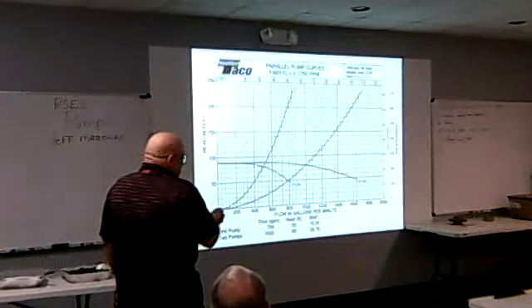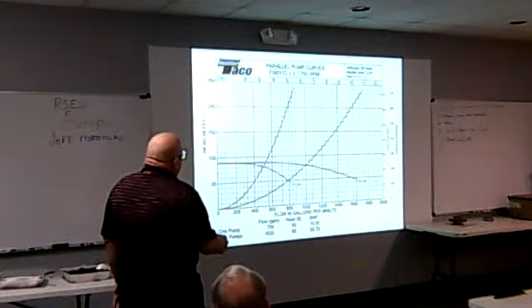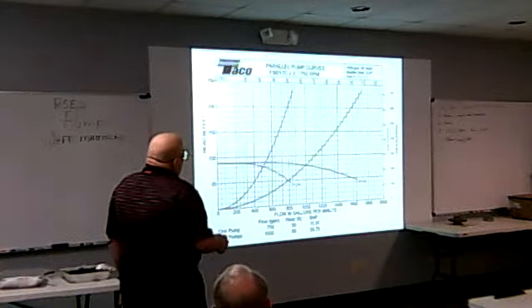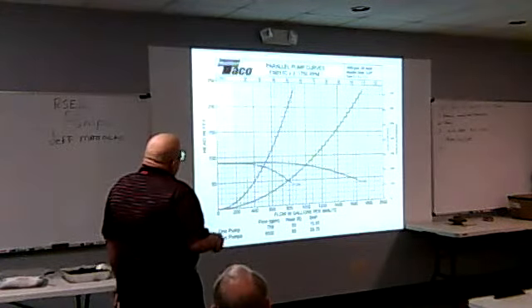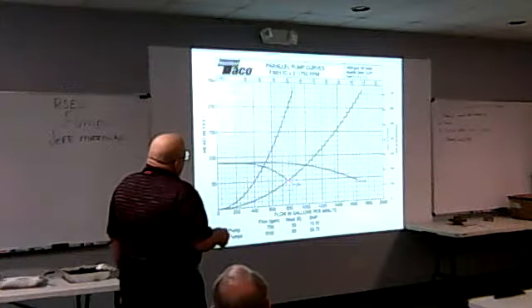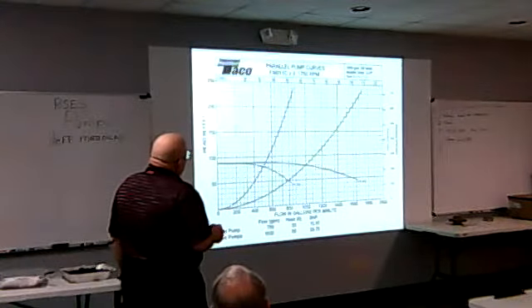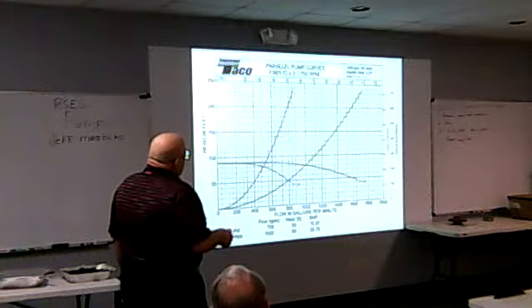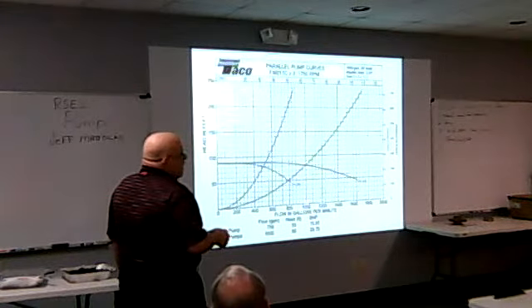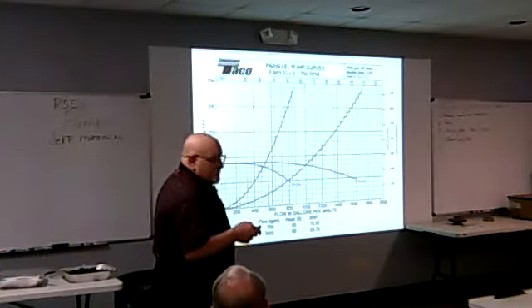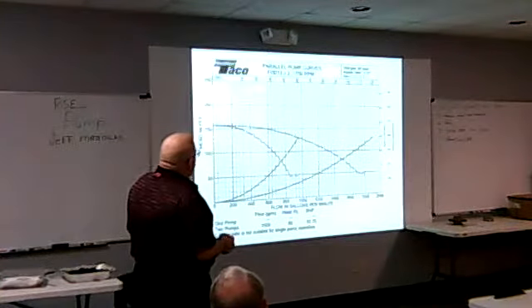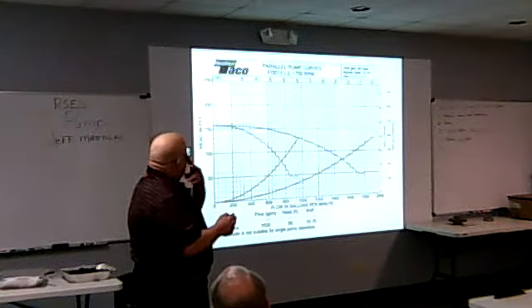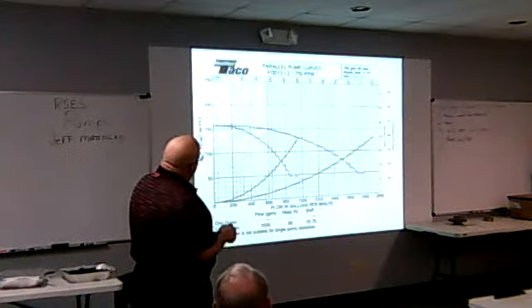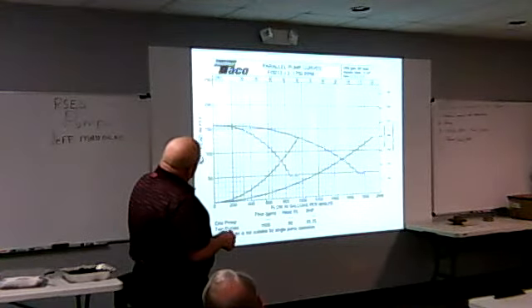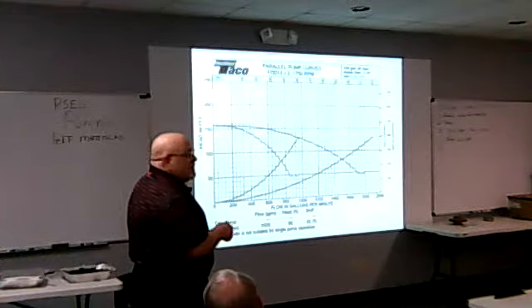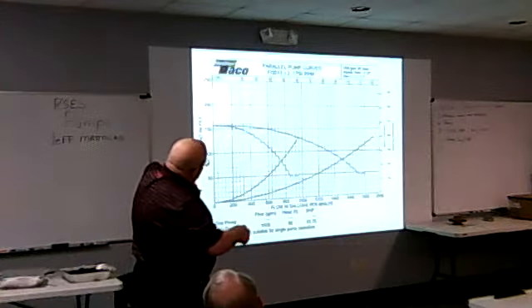And here's another curve like we talked about. If you have a very, very flat curve, and it's not too flat, here's our original system curve. Here's our selection again. We did the second curve just by doubling this out. Here's what I'm going to get by picking up the second pump: 200 GPM is all we picked up. The steeper the curve is, the more we're going to get. Here, this one is a steeper curve, and we picked up a lot more flow.